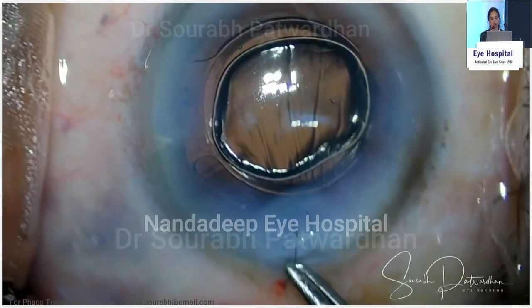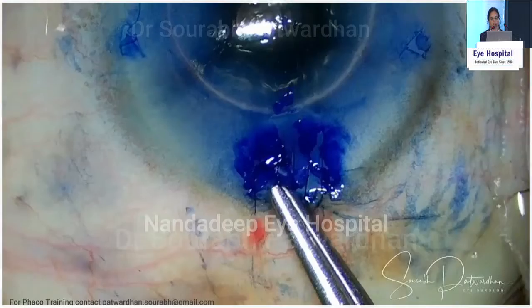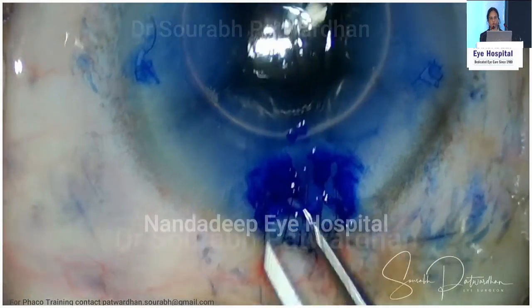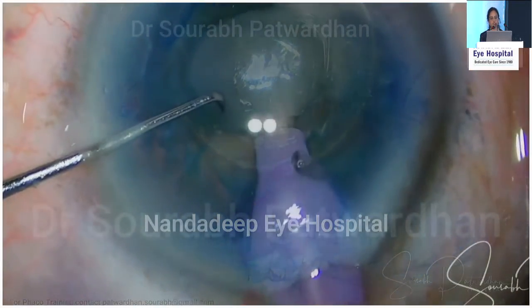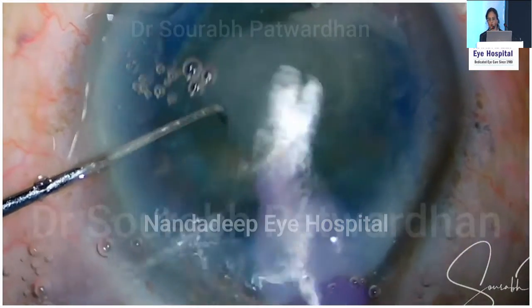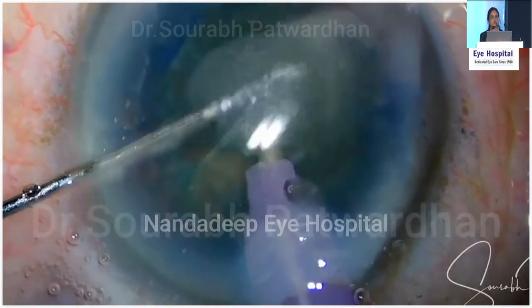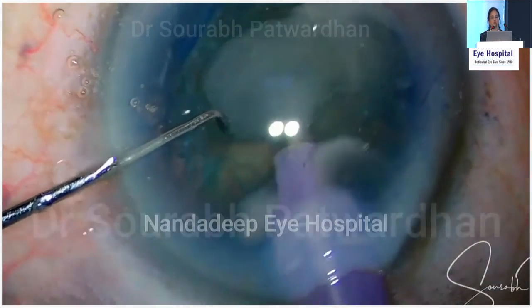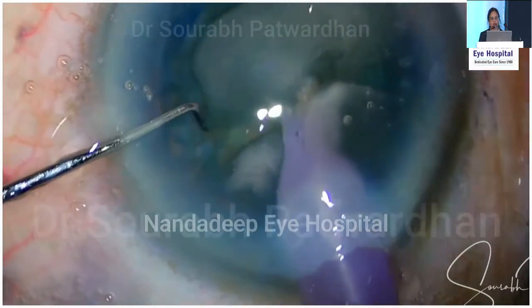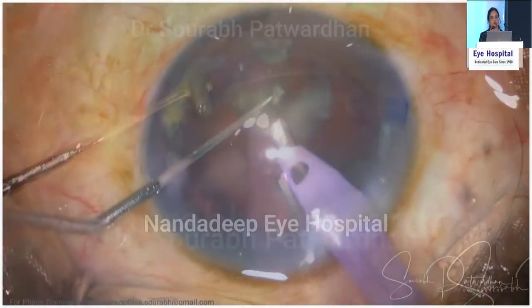This Phaco tip blockage can also be identified if you are doing a quadrant removal and suddenly the pieces stop coming to your probe. An easy way to remove the blockage in your Phaco probe is to just put it in a fluid chamber and start the Phaco longitudinal power.